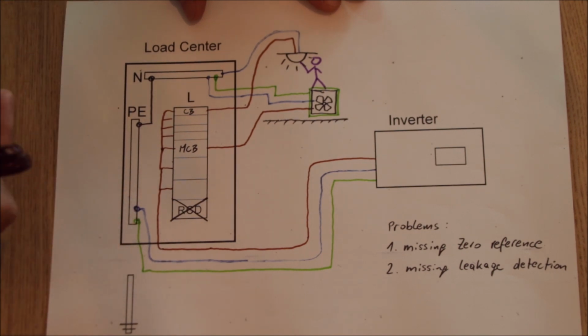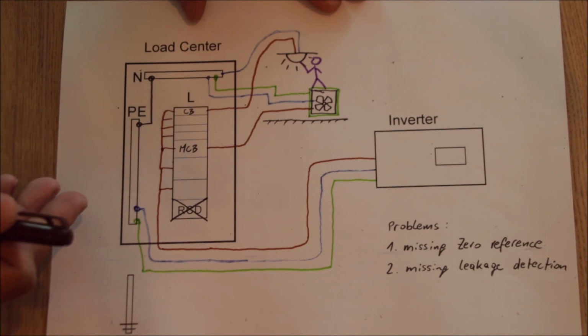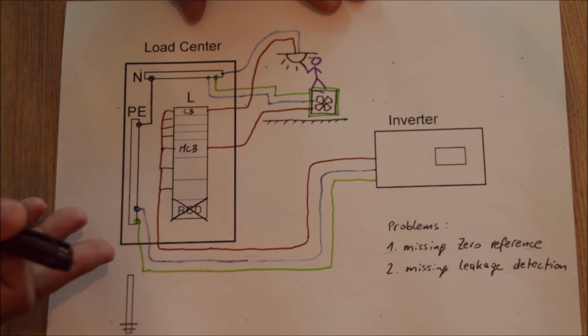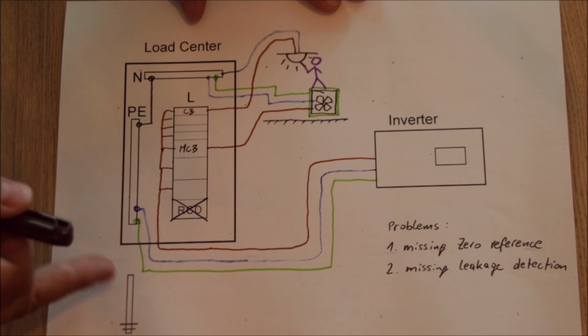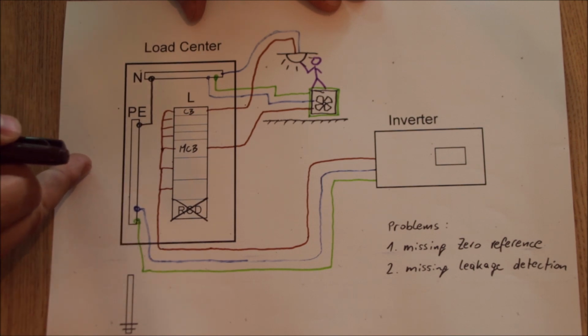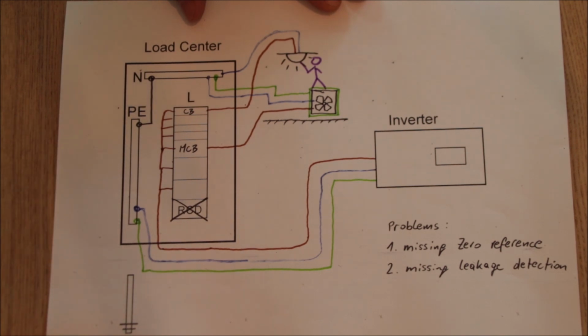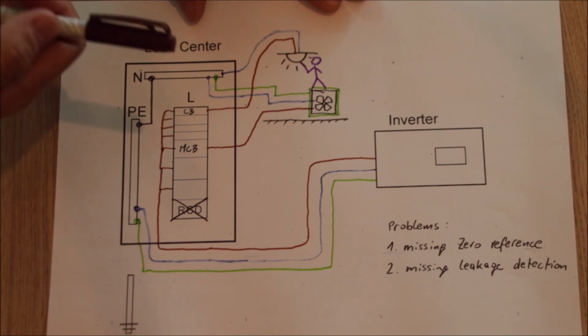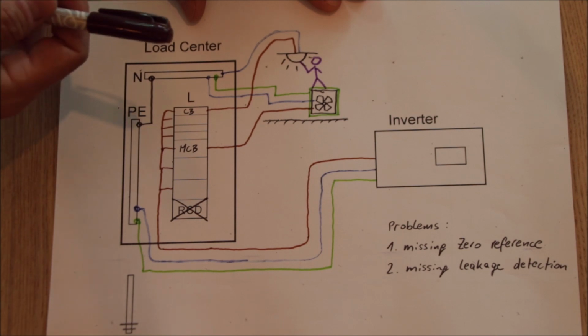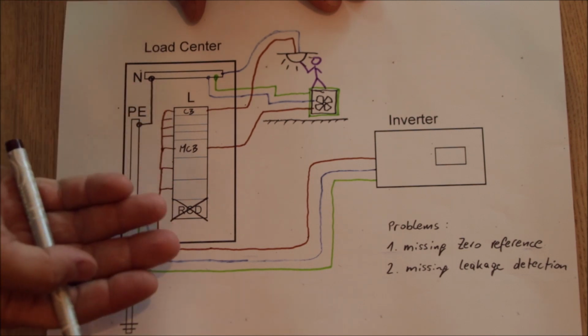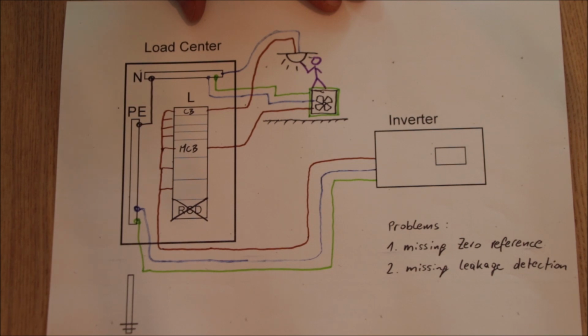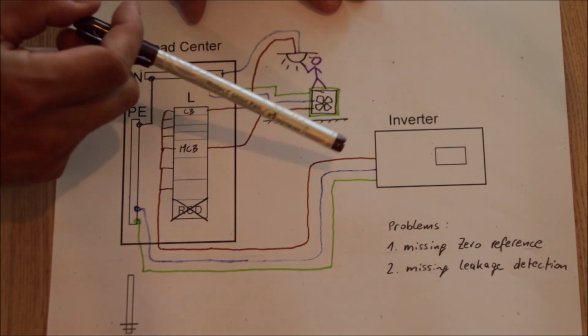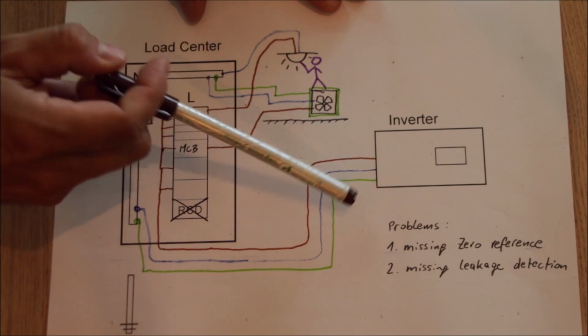And then he says that he followed the manual about bonding, and that the manual says he should bond earth and neutral inside the panel, right, in the main panel. But I've checked the manual from the LV6548 and I did not find anything about this. The only thing I found mentioned in the manual was that they say that grounding must be done via an external source of ground.